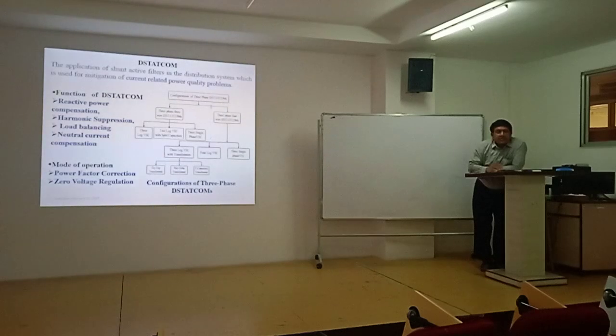On the primary side we have connected zigzag, so that in each phase the current is going to neutralize there only. While in case of the second one, we are going to supply neutral current to the primary side of the star, and that one is going to transfer to the secondary side. In that we have a delta circulating current. With that current we want to circulate inside the delta only. But that also has some limitation: how much can we flow? Here we want to neutralize, but here we want to flow. In this case, one more connection is there, but this connection is somewhat typical. In the T connection we need some special design of transformer also.